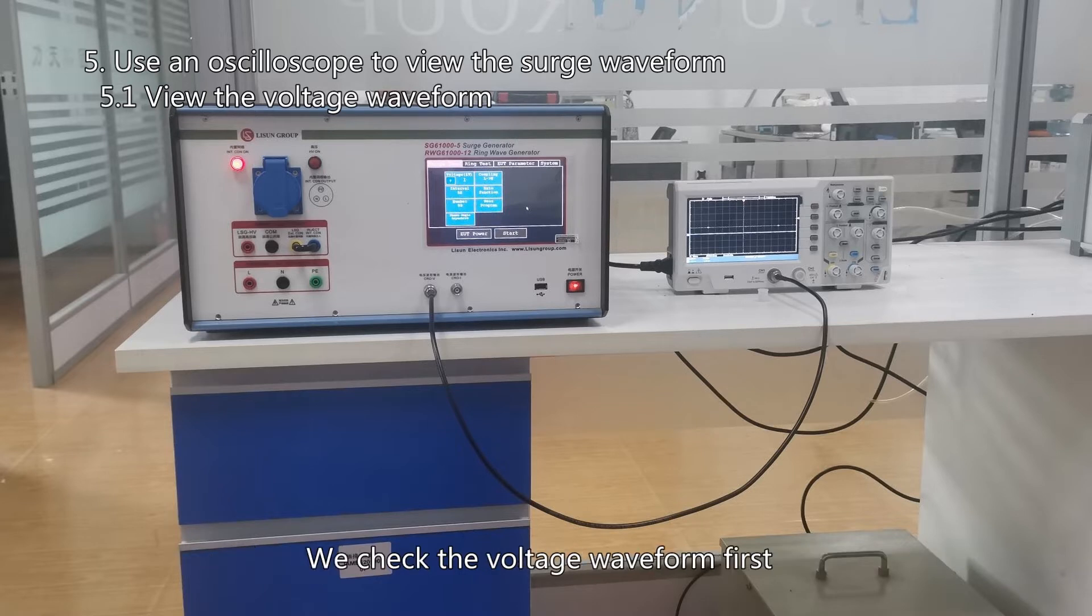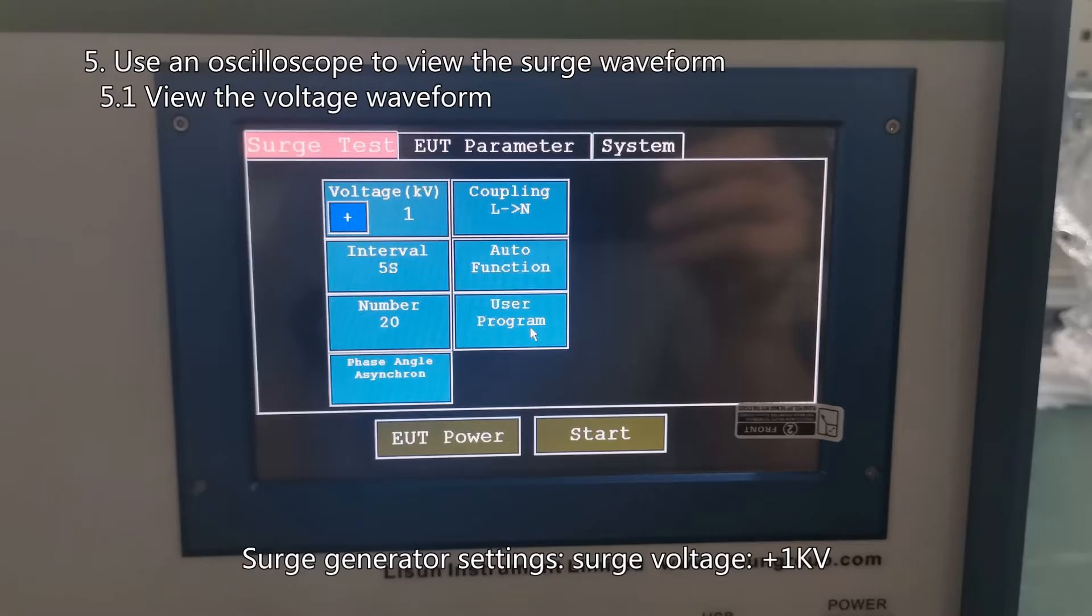We check the voltage waveform first. Surge generator settings: surge voltage, positive 1 kV.